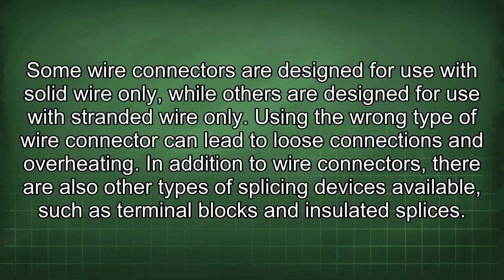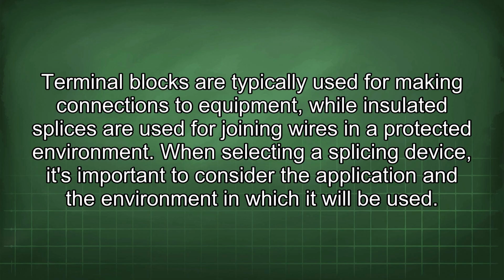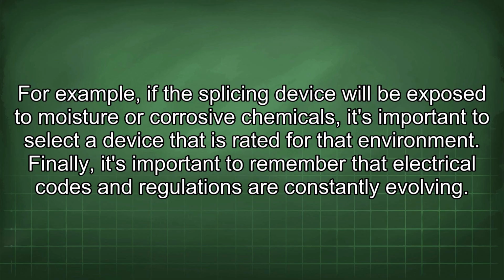In addition to wire connectors, there are also other types of splicing devices available, such as terminal blocks and insulated splices. Terminal blocks are typically used for making connections to equipment, while insulated splices are used for joining wires in a protected environment. When selecting a splicing device, it's important to consider the application and the environment in which it will be used. For example, if the splicing device will be exposed to moisture or corrosive chemicals, it's important to select a device that is rated for that environment.